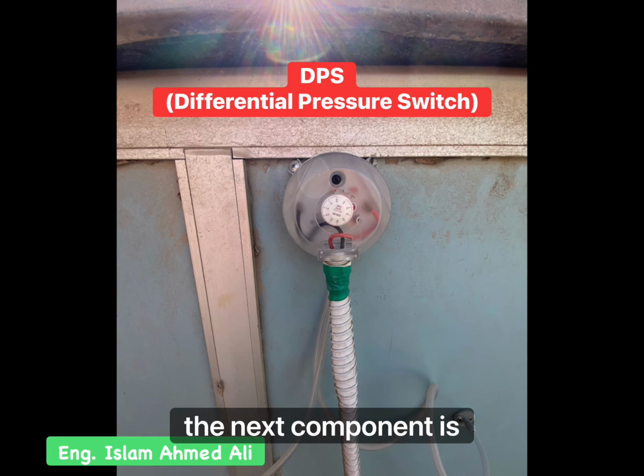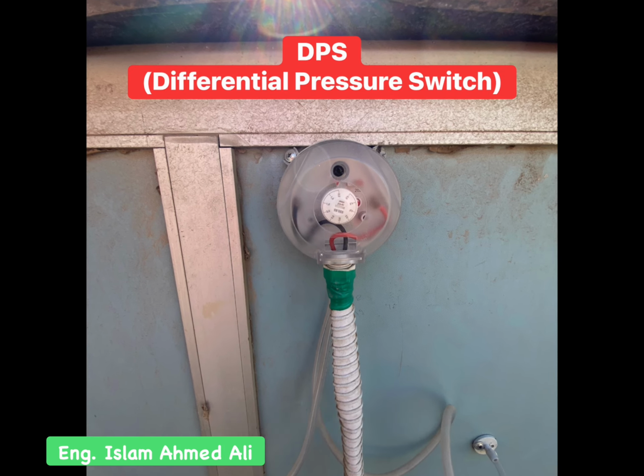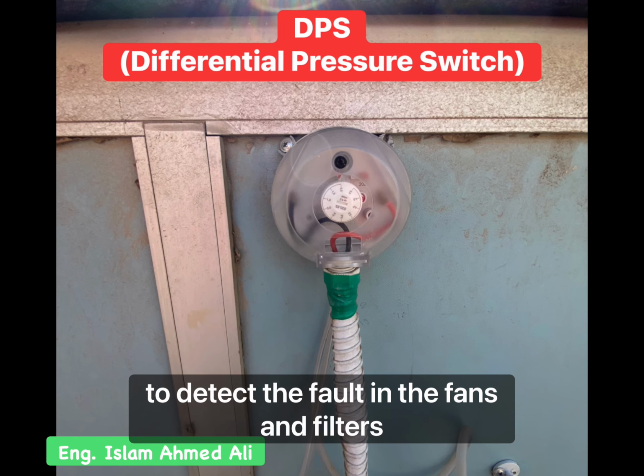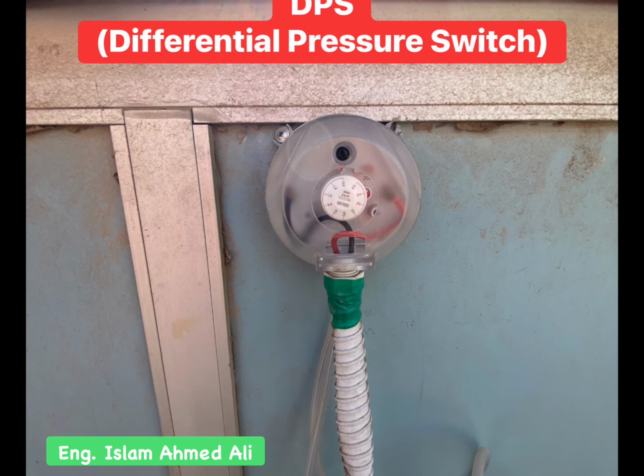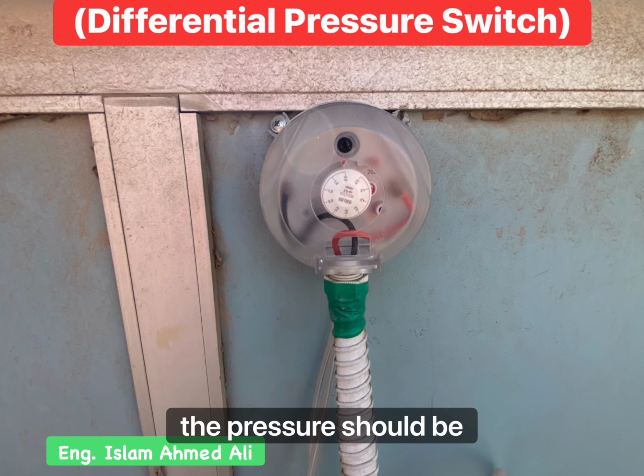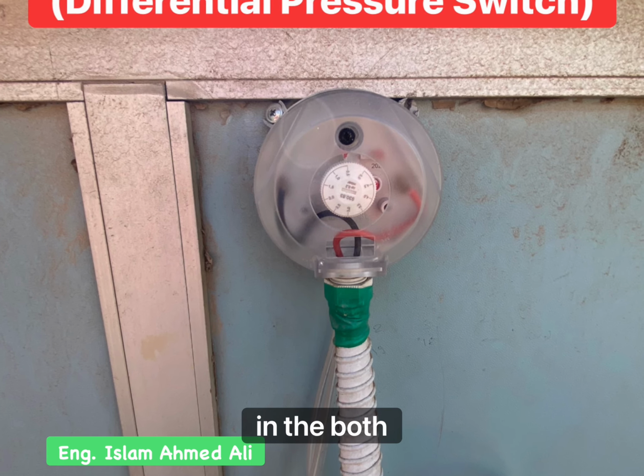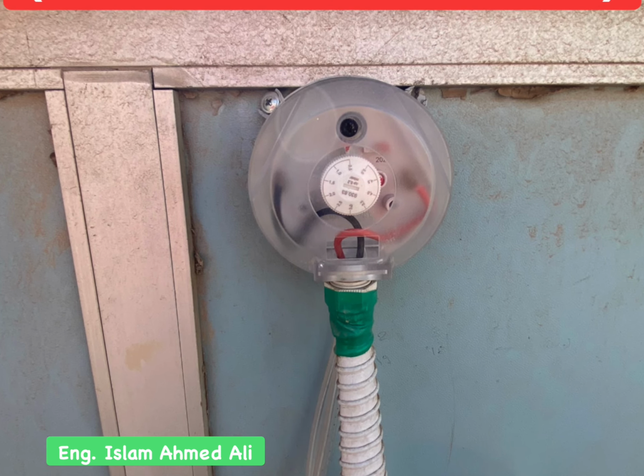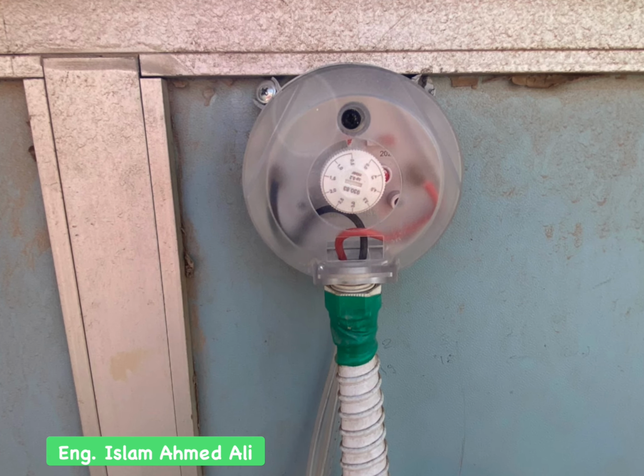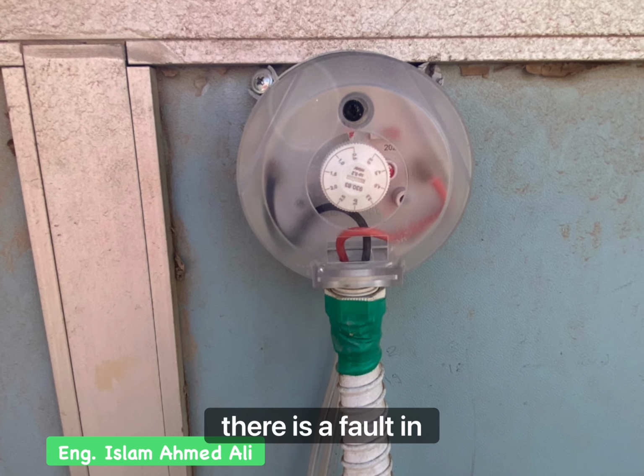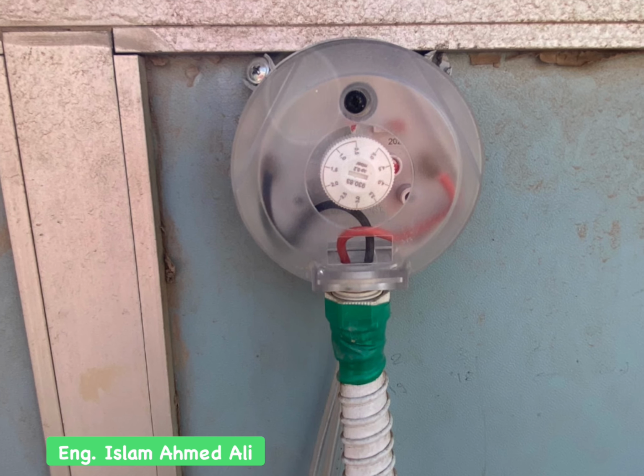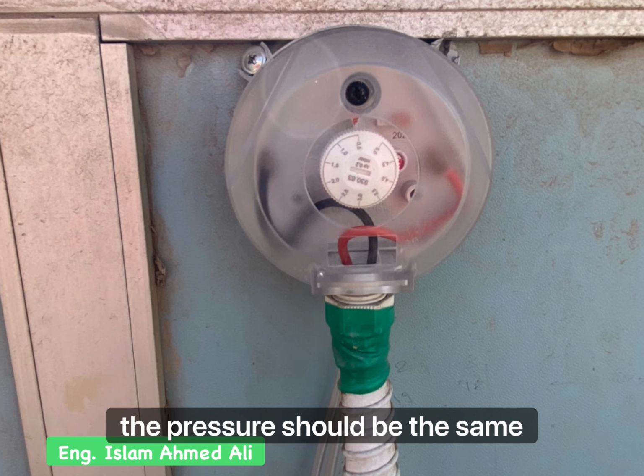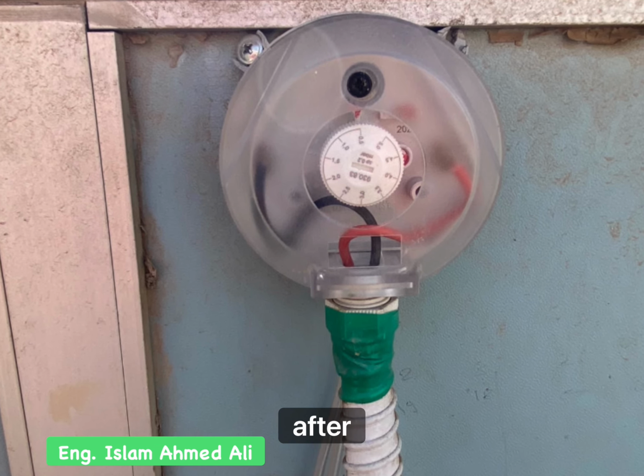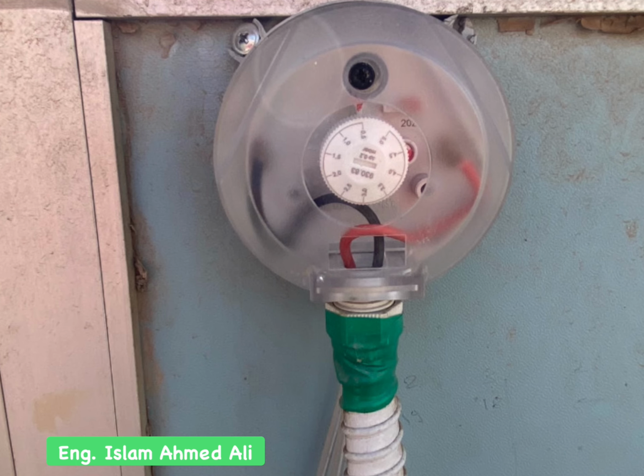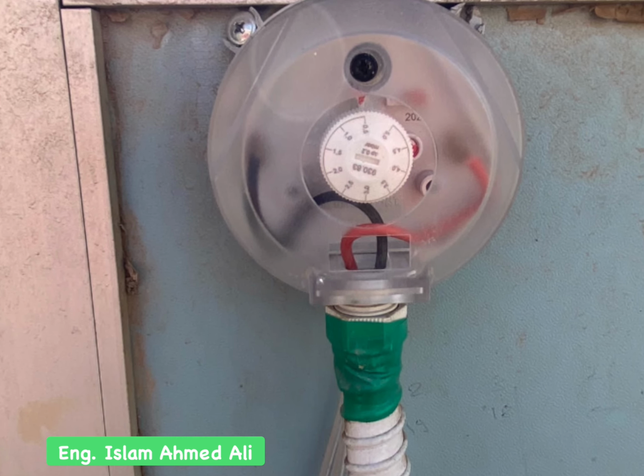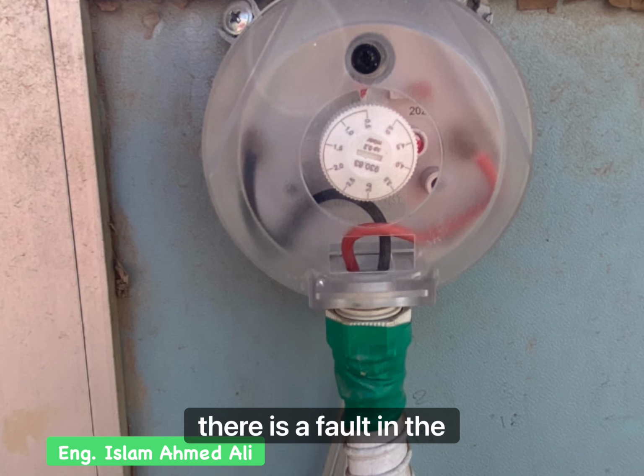The next component is differential pressure switch, which is used to detect faults in fans and filters. In fans, the pressure should be different on both sides. When the pressure difference is 0, that means there is a fault in the fan. On the other side, in the filter, the pressure should be the same before and after, but when the pressure is not equal, that means the filter is not clean, so there is a fault in the filter.